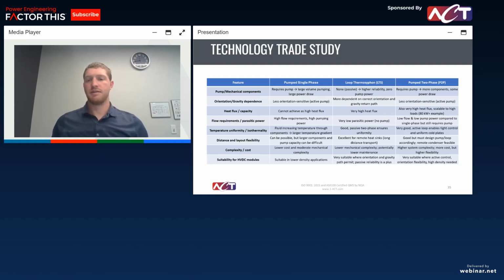Just a trade study on single phase versus loop thermosyphon versus pump two phase. So with your loop thermosyphon, you're reducing those mechanical components, so higher reliability. You don't have that pumping power, but you are dependent on gravity. Loop thermosyphon and pump two phase are going to be able to meet higher heat flux components, much over 100 watts per centimeter squared, whereas pump single phase is going to have a much harder time with that. Isothermality as well is another big advantage for the pump two phase and the loop thermosyphon.